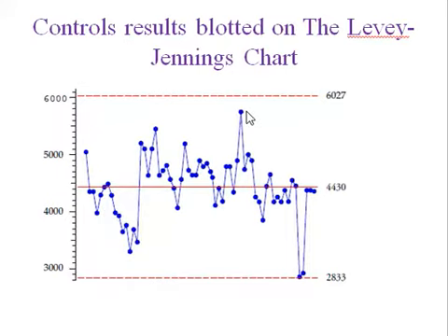Control samples or solutions should be used on a daily basis, specifically with each run during a month. The day-to-day control results should be used as a set of data to calculate the mean and standard deviation, and to plot the obtained data on the Levy-Jennings chart to observe whether there is a trend shift, or a value outside the 2SD border or outside the 3SD border.